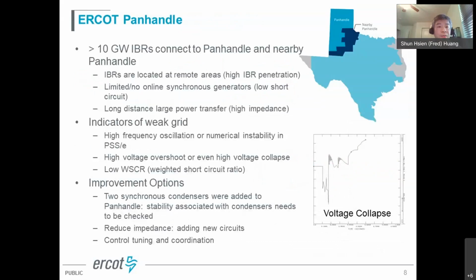The last example is the ERCOT panhandle case. The previous one was localized, but here, once more inverters started connecting, we began observing that the weaker grid challenge can expand to an area or region-wide issue. The panhandle is a typical example we're addressing right now - it's the northwest corner of Texas, which has mainly a single 345 kV transmission circuit with inverter-based resources. We have almost zero load and zero synchronous machines in this area, transferring power a long distance to the load center in east Texas. Today we have more than 10 gigawatts of inverter-based resources connected to the panhandle and nearby area.